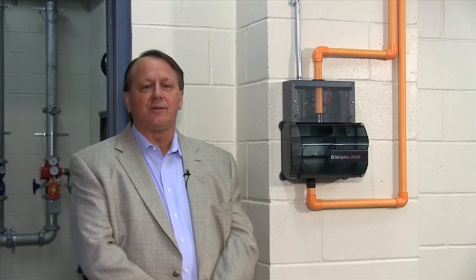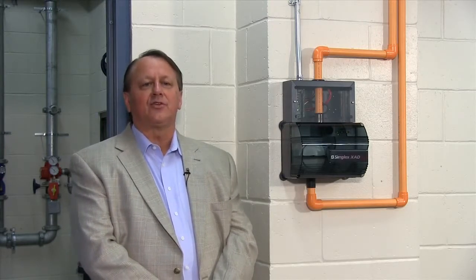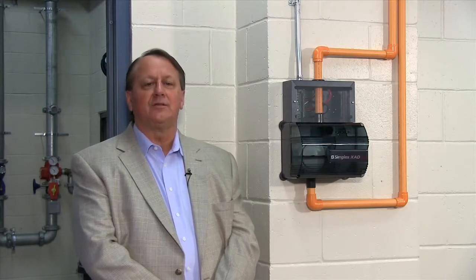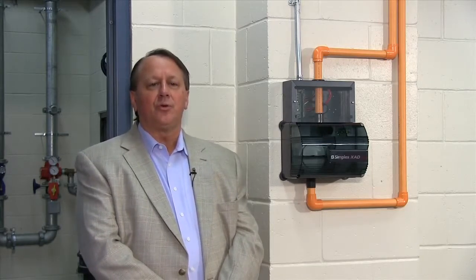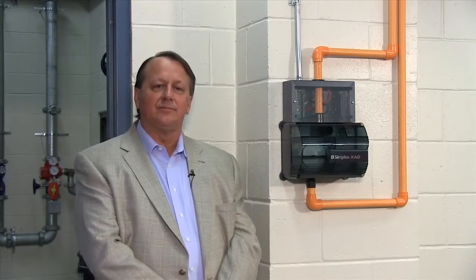As an industry, we have traditionally approached duct detectors the same way, by attaching them directly to the duct and installing sampling and exhaust tubes into the duct itself. The tubes allow the air flowing through the duct to be sampled, tested, and exhausted back into the HVAC system.